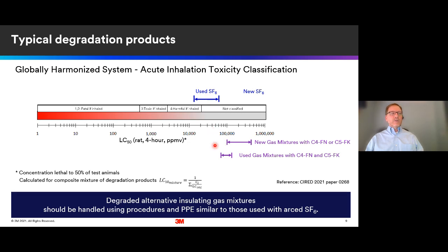When the same thing is evaluated for the SF6 alternatives, you can see the new gas mixtures are again in a non-classified area. Again, the hazard is so low as to not warrant any kind of a hazard classification. But the used gas mixtures are a little bit more hazardous. The LC50s are lower. These are from tests that were conducted either from a series of current interruption sequences or an internal arc failure condition. And it starts to get into the same range where you see used SF6. So as a result, industrial hygienists would typically advise that the handling procedures and the personal protective equipment that are used today with arced SF6 should be applied to the used alternative gas mixtures as well.